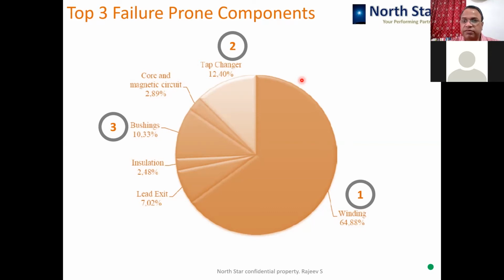Third is the bushing failure, which is 10.33%. Bushings, as I look at them, are the link between the internal of the transformer and the external world. They are connecting both worlds, and they are the live part directly in contact with the environment, and all the environmental brunt is faced by the bushings. So bushings are punished in a big way, and because of failure of the bushings, the transformer also fails. If you look at the winding failure, it might be possible that many of the windings have failed because of problems in the bushings. So monitoring of the bushings and their testing from time to time is very much required, and those are components which have to be maintained very, very carefully and on time.